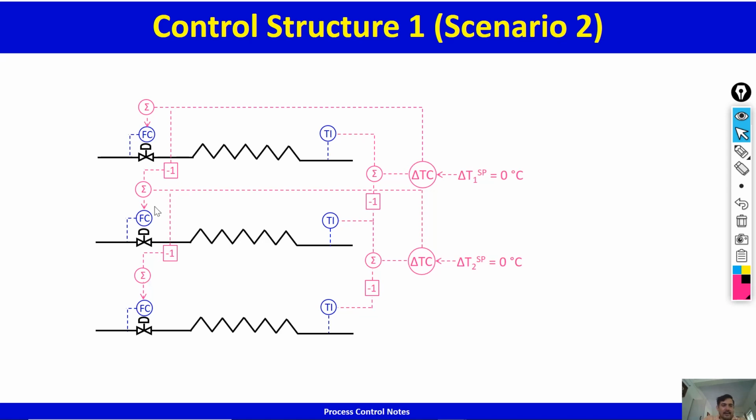Okay, and you'll be wondering why I have this summation here. This summation is essentially for F dot control. What if I change the value of F dot? So you have the F dot set point, and this set point can be changed. You have the current F1 by F dot ratio at which the process is operating. So the F dot set point is multiplied by the current ratio, and this is the flow that F1 should be, and the magenta lines are corrections to that flow for heat pass balancing.